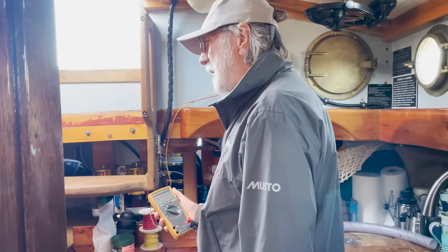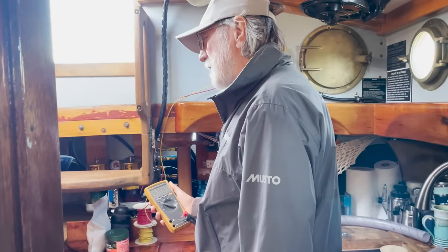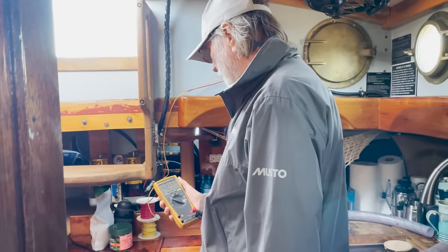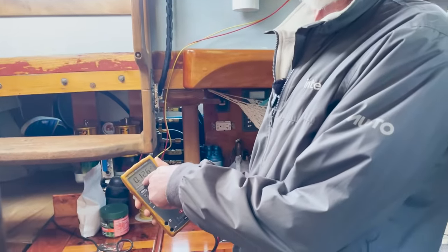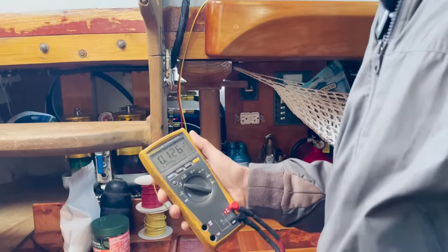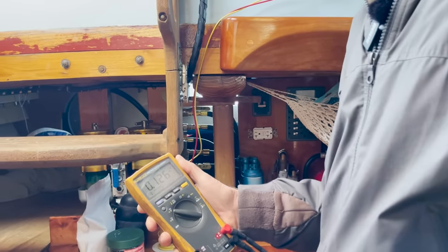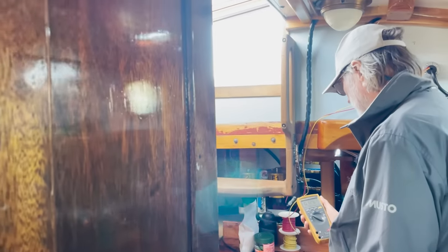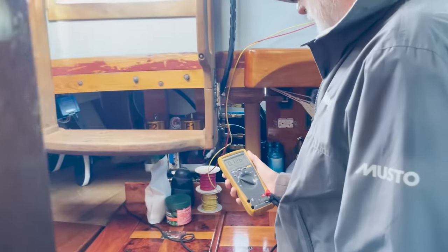So for us to get a reading, we've got to have a path from... Oh, here we go. Was that on a through hole? That was on a bronze floor. Can you see? Yeah, see, 0.126. The bronze has a much lower natural voltage. So whatever's at 0.2 of a volt, if there's any circuit between them, would get corroded to protect the lower voltage metal.